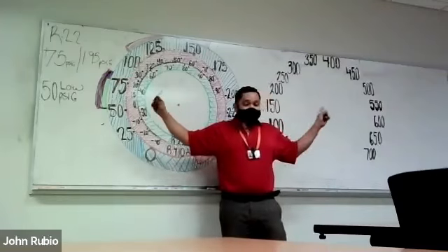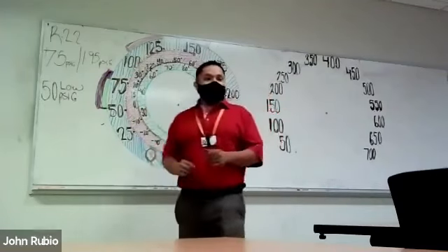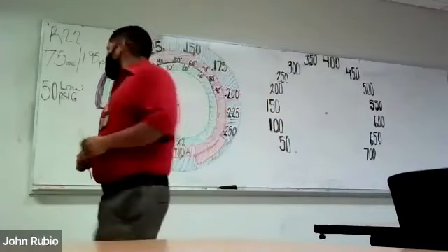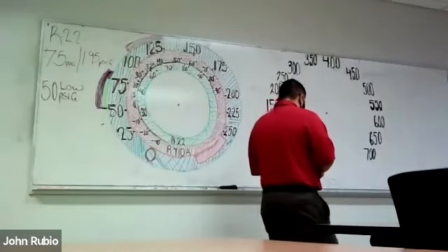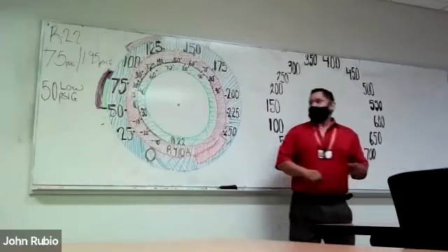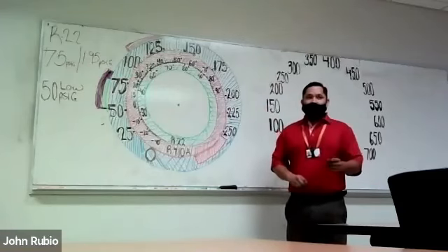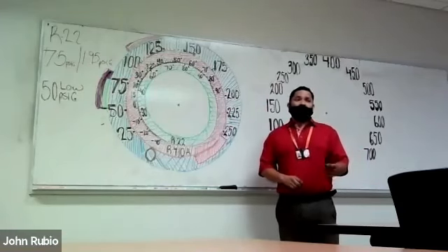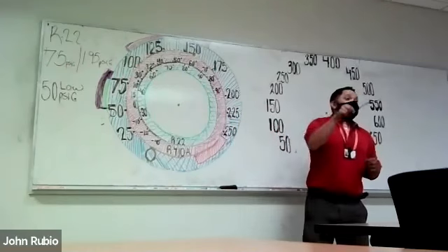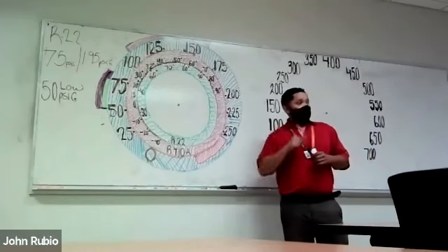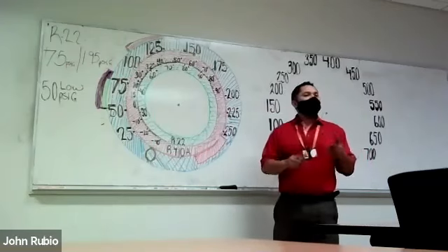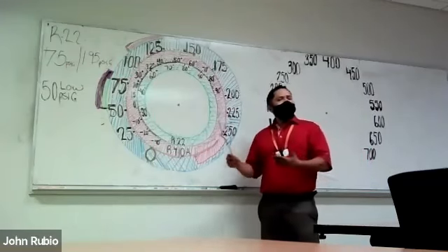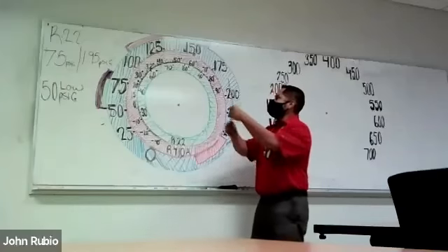Because now we need to see what's happening in both sides of the refrigeration cycle. So why do we freeze at 50? Why will you always freeze at 50? Because of temperature pressure charts. And instead of looking one up, every time you look at your gauges, there's a temperature pressure chart looking at you, waiting for you. It's a lot easier to confirm superheat and subcool when you already have one of your temperatures right in front of your face.